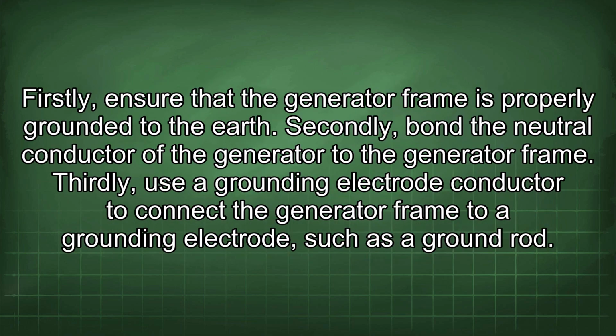Firstly, ensure that the generator frame is properly grounded to the earth. Secondly, bond the neutral conductor of the generator to the generator frame. Thirdly, use a grounding electrode conductor to connect the generator frame to a grounding electrode, such as a ground rod.